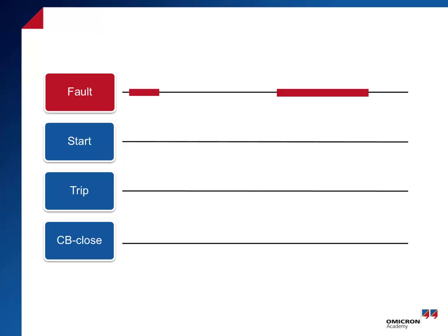In the graphic, you see the signals for the automatic reclosing. When a fault is detected on an open line, the relay trips and the line is disconnected. Once a dead or delay time has elapsed, the line is automatically reconnected. If the fault persists, the line is disconnected again.